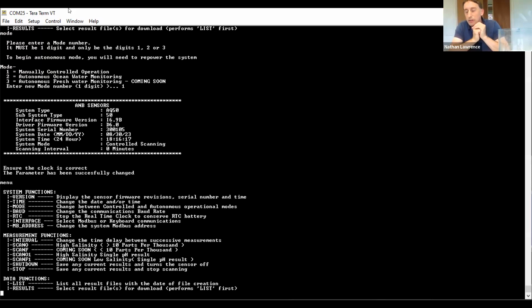We have a scan-O function, which is for the higher salinity conditions greater than 10 ppt, and a scan-F function, which we're currently rolling out and developing the firmware for, which will go to the lower parts per thousand measurement. A scan-O1 function allows you to turn on the sensor, type scan-O1, and it will take a single measurement and then turn off. So these are for people that want to poll their sensor, take a measurement, and then turn it off straight away. And that's the way the sensor runs. You can continually poll the sensor using a scan-O1 type function. We also have the shut down and stop functions at the end, and I'll show you that.